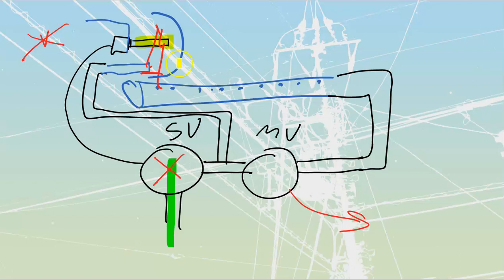Other reasons that you could have lost it is if I have covers off on my device. Sometimes if there's a natural gas shutdown or disruption, or you get small earthquakes here, the gas systems will shut down because they don't want to be leaking gas, so people's pilot lights will go out. And then what people do is they open up the side door of their furnace or of their hot water tank, and because it took them so long to find that stupid screwdriver, they'll just decide to leave that cover off. Covers need to go back onto these things because the covers prevent us from having backflows that come down the B vent, that's the chimney, push through the actual device and push out of that little door. If we have that, those backdrafts will be able to blow out pilot lights in a lot of cases. So make sure those covers are back on. That's when dealing with my thermocouple.